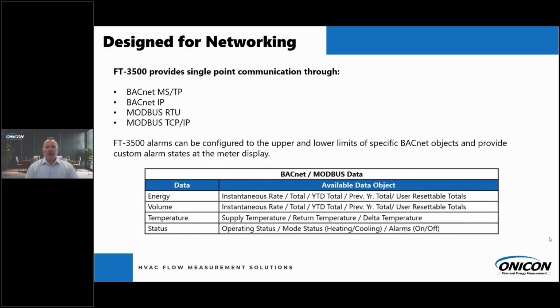So what's great about this meter is that when we designed it, we had the networking in mind. And we actually updated the stack now, so you're able to provide BACnet and/or Modbus, whether that's RS-485 and/or IP. And if you notice there with our alarm settings, you can set the upper and lower limits for BACnet objects. And as you see on the table, those are some of the objects and registers available on that serial communication.